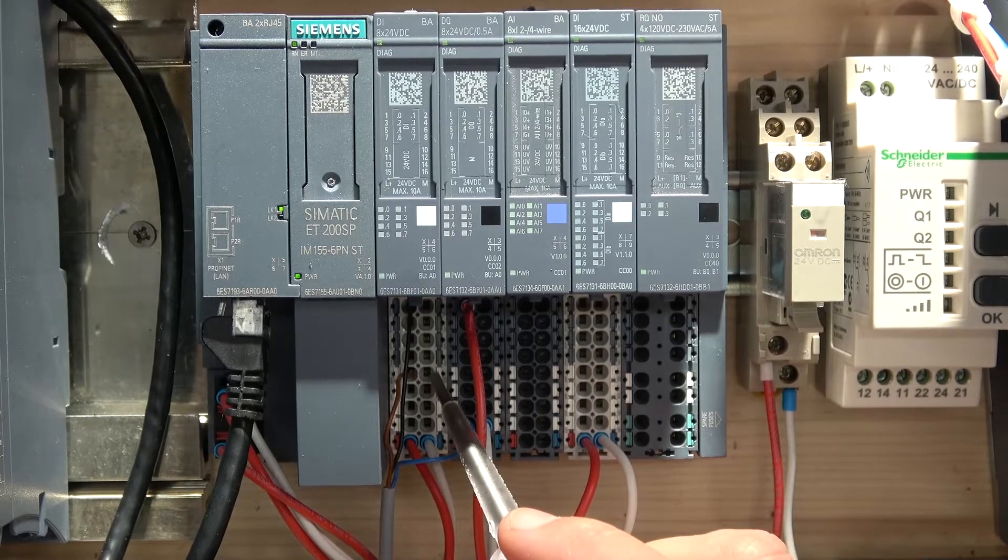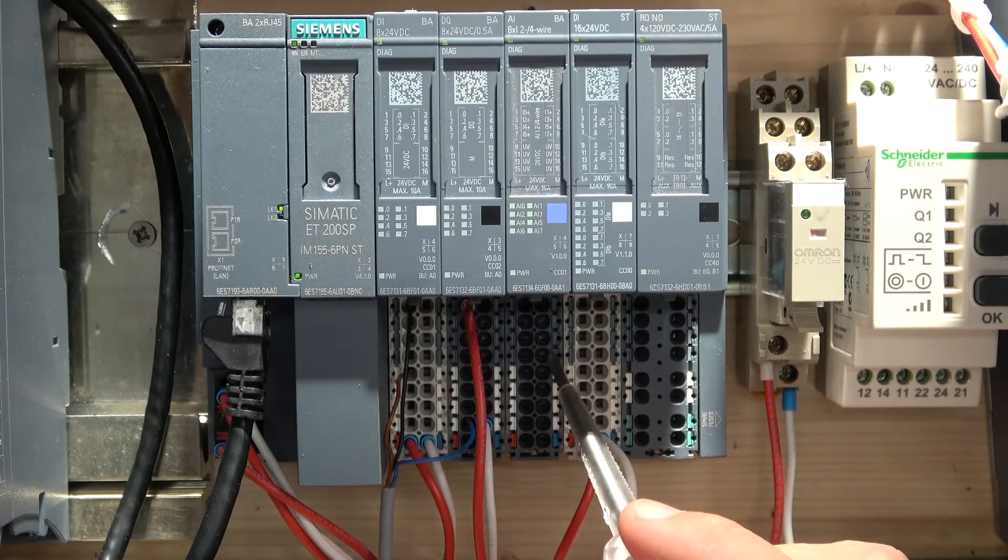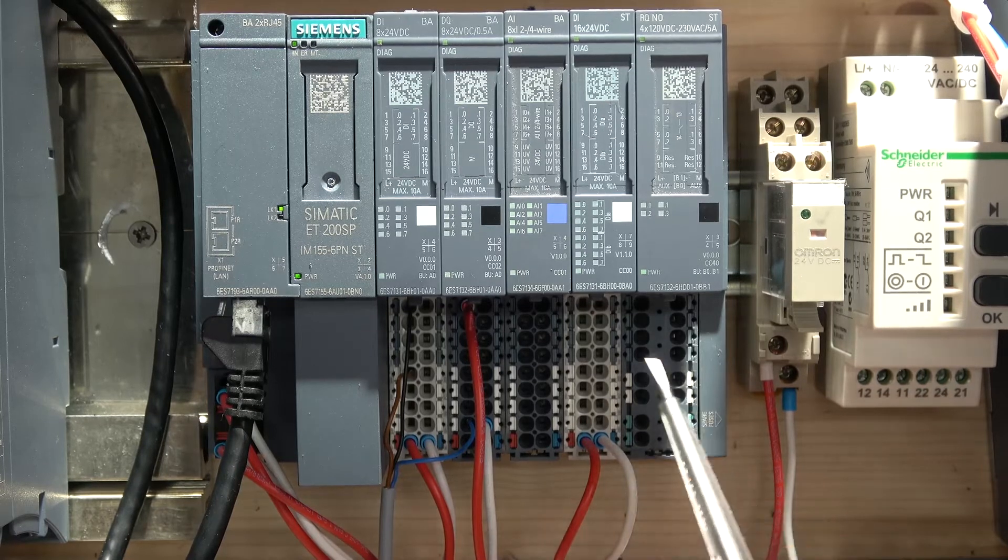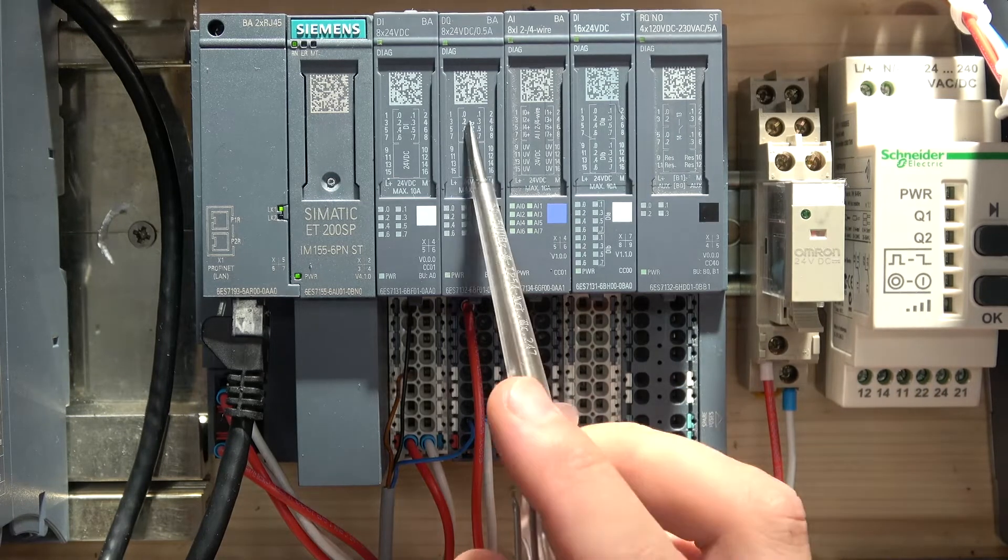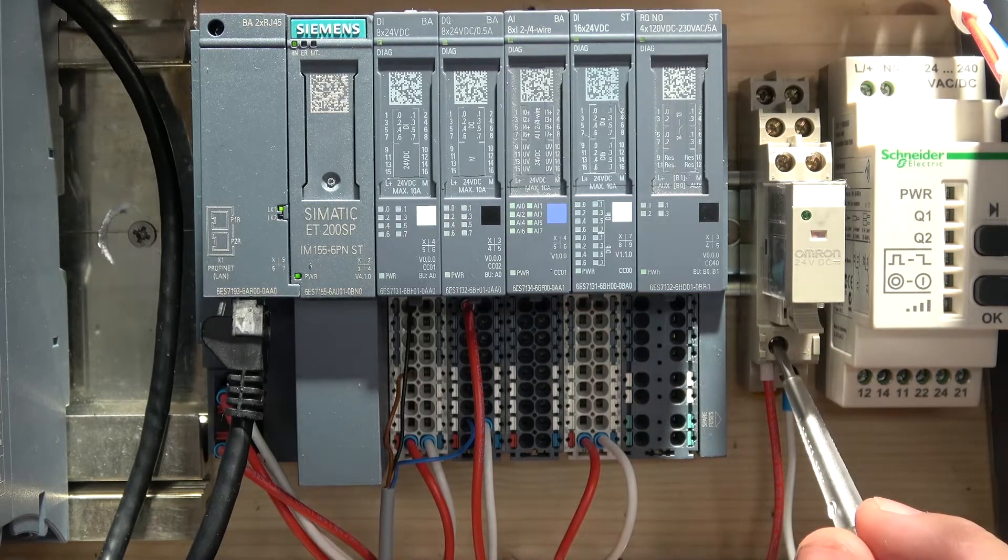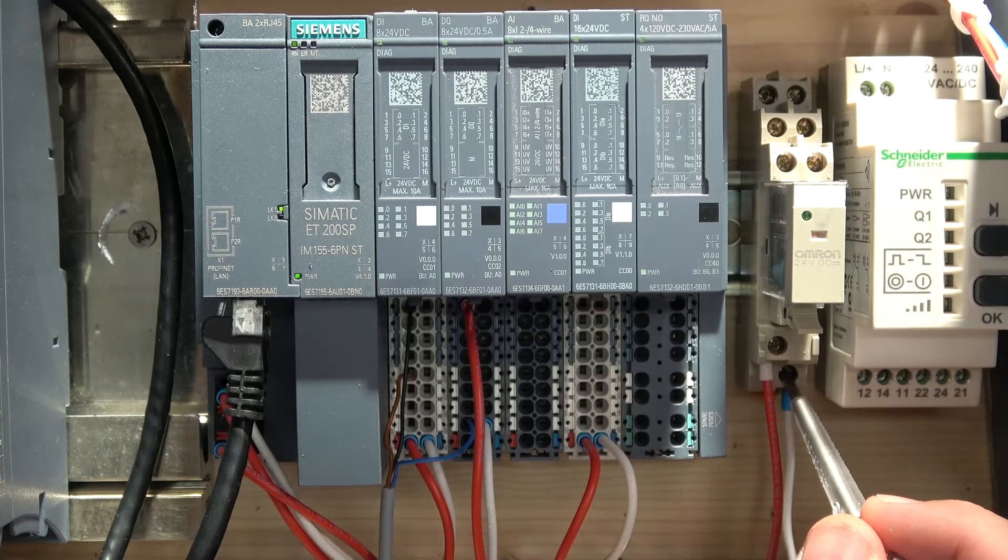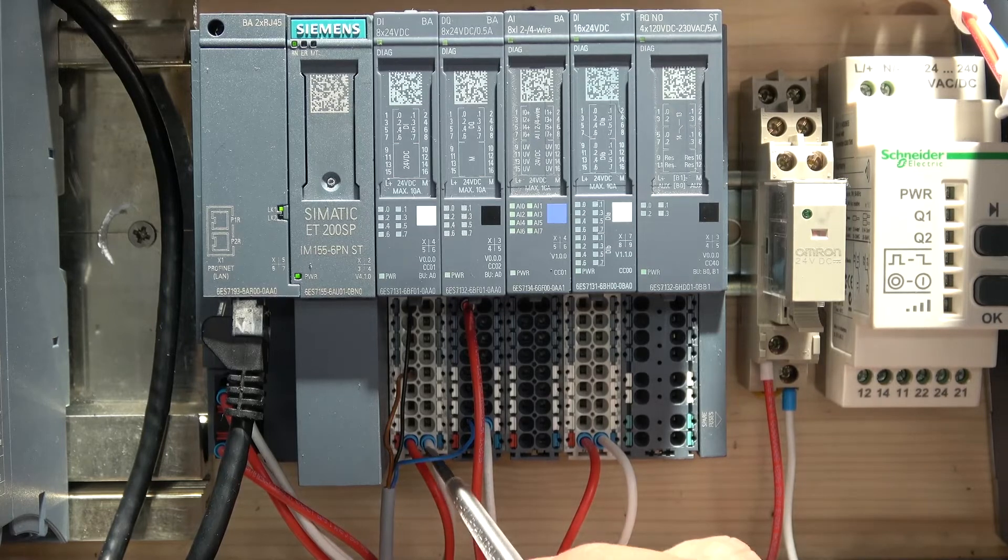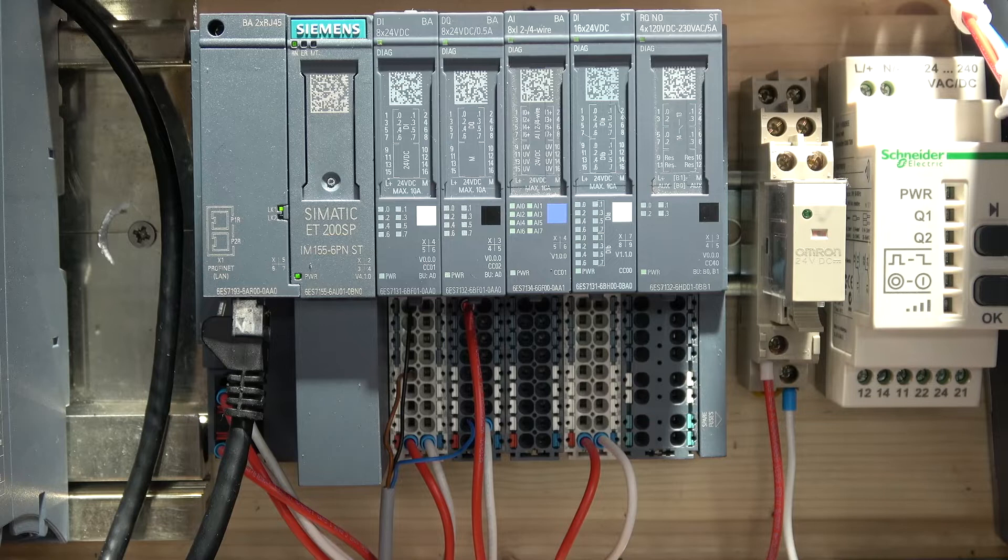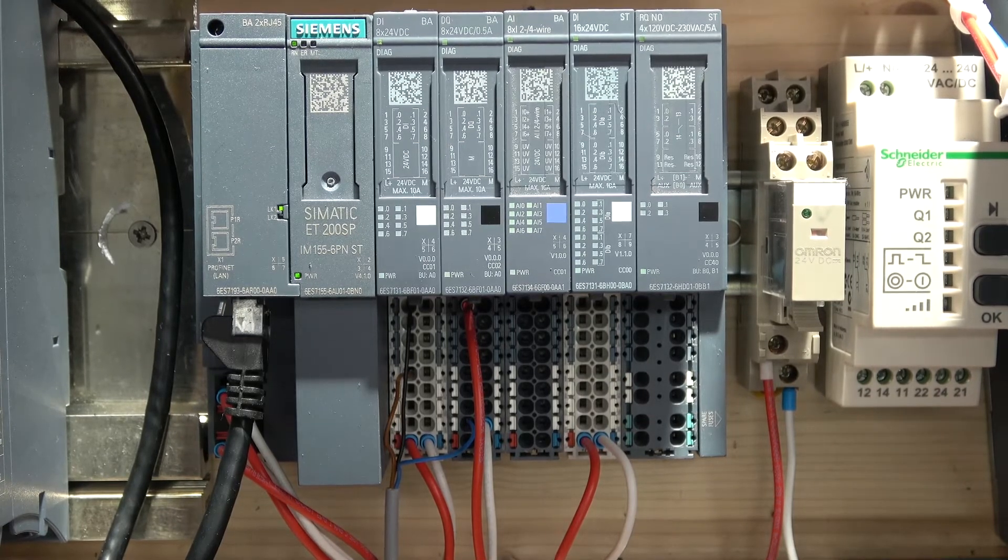Remember, we spoke about this at the very beginning. This white one segregates the sections of specific setup. Section one all the way from there to there, section two continues from there to there. And when it comes down to outputs, I have outputs which are transistor outputs, so it's outputting 24 volt DC, sending plus to my relay, and I'm also taking my negative and powering my negative part of my relay. The key is to pay attention to what is powering the card itself and where the power supply is coming from. You can't mix them.